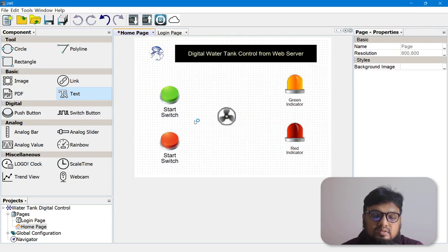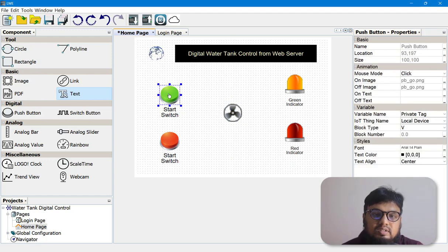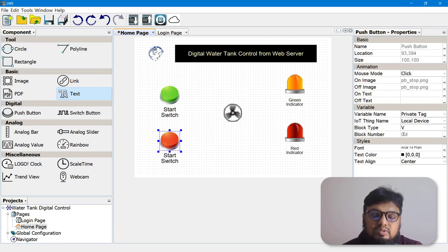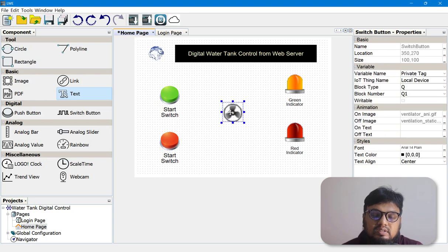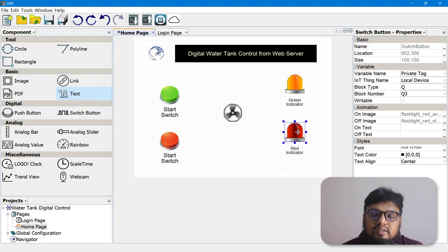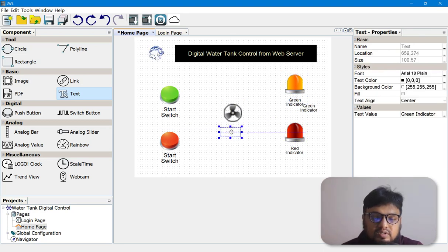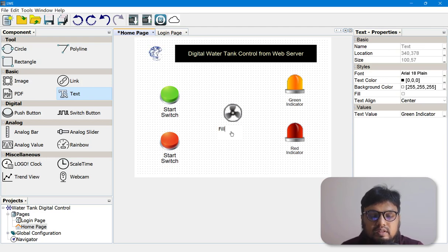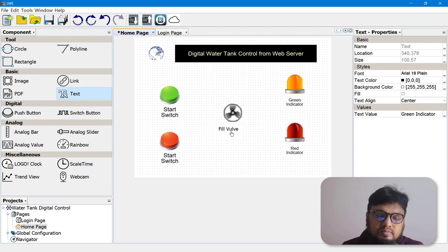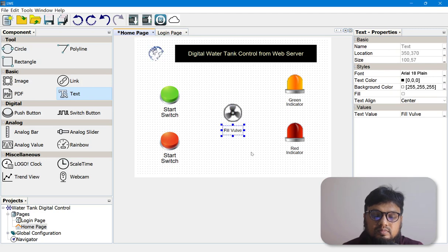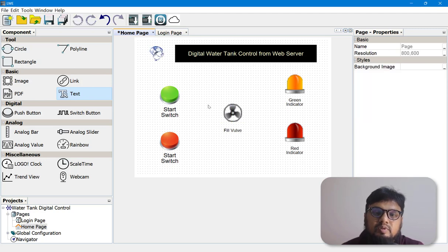Let's do a final recheck: the start switch is on V0.0, the stop switch is on V0.1, the fill valve output is on Q1, the green indicator is Q2, and the red indicator is Q3. We can also put a text label — 'Fill Valve'. If your programming and designing is done, you can upload this file to your LOGO PLC.